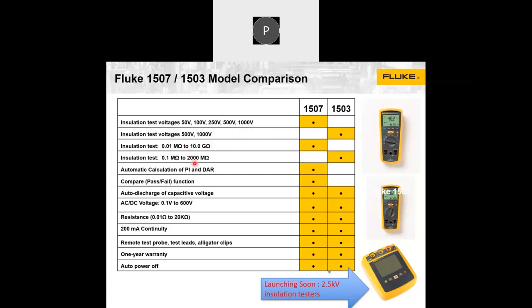The insulation resistance range also is very high, that is 10 giga ohm in this model and 2000 mega ohm in this model. That means detailed insulation analysis can be done using these products, and pass-fail analysis also you can do, including PI and DAR. You may not do this on a regular basis, but you can decide, maybe for a new cable, to understand what exactly the PI (polarization index) and DAR (dielectric absorption ratio) are, and find those values.